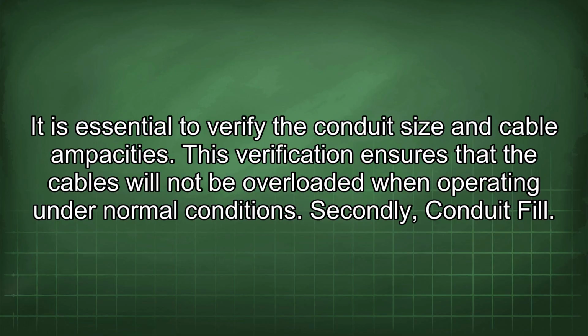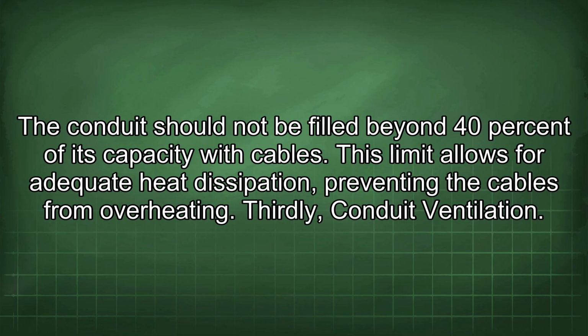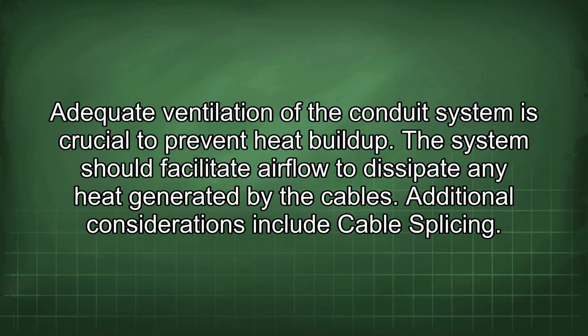Secondly, conduit fill. The conduit should not be filled beyond 40% of its capacity with cables. This limit allows for adequate heat dissipation, preventing the cables from overheating. Thirdly, conduit ventilation. Adequate ventilation of the conduit system is crucial to prevent heat buildup. The system should facilitate airflow to dissipate any heat generated by the cables.